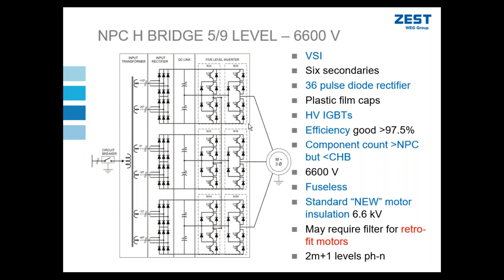We use a similar topology in the output inverter section that we use in the NPC 4.16 kV version. So you can already start seeing the hybrid between the NPC and the isolated supplies of the H-cell. Essentially, each set of two secondaries is an isolated supply to an inverter, which now becomes your power cell of your H-cell inverter. So we've got three similar H-cell topologies, but each of these power cells is able to have the switching combinations of an NPC topology. So this is something of a good go-between if the application requires it.